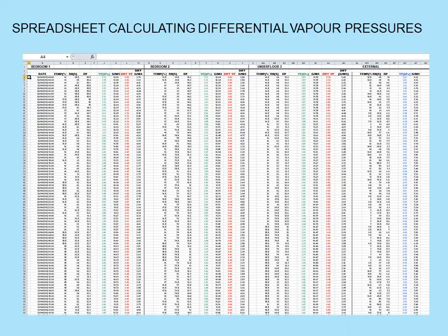However, with a data logger, you may collect anything between sort of 500 and 2,000 bits of data. In this case, we were collecting it at half-hourly intervals. So sticking to something like a psychrometric chart will take you a month of Sundays. The easiest way is to use a spreadsheet that's already set out. One simply puts the data into the spreadsheet and all the calculations are done for you.